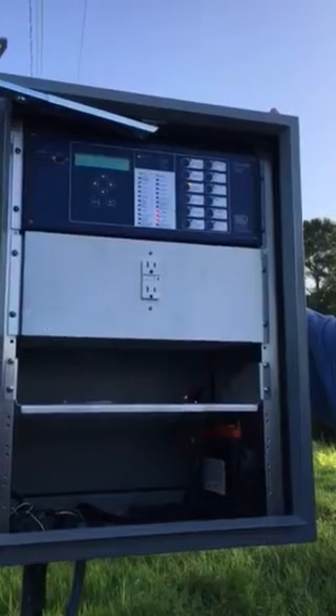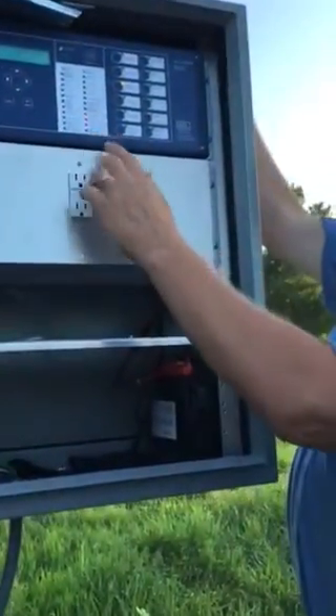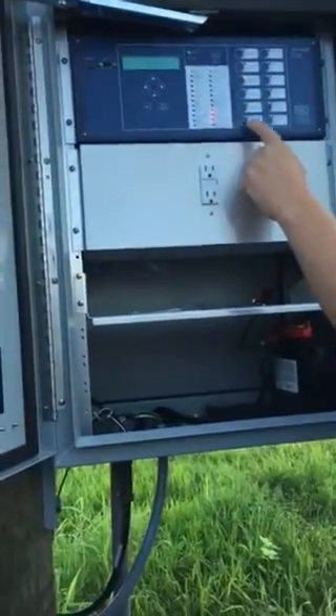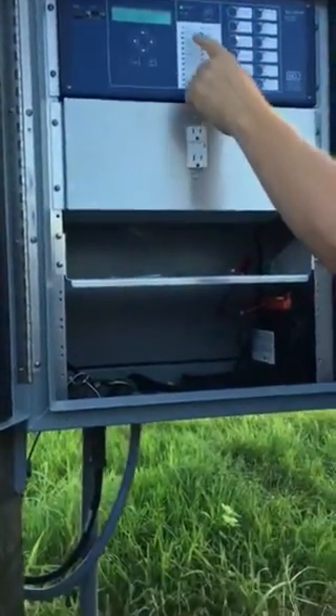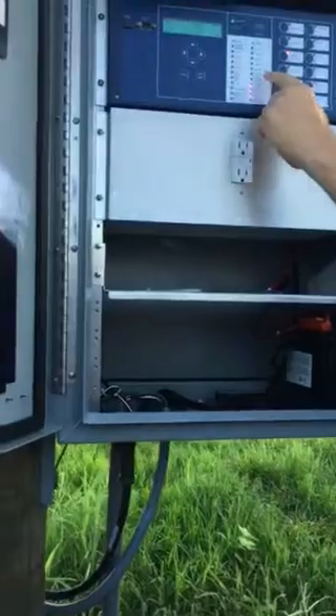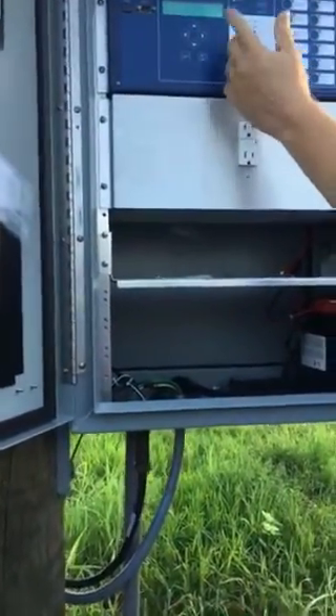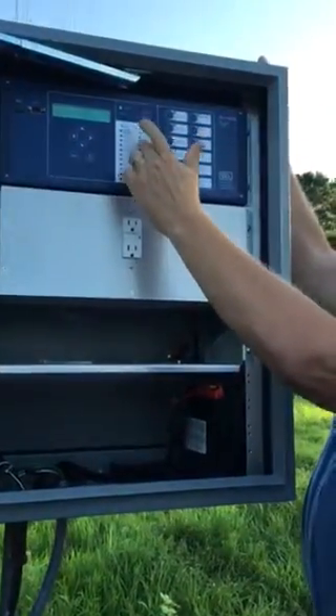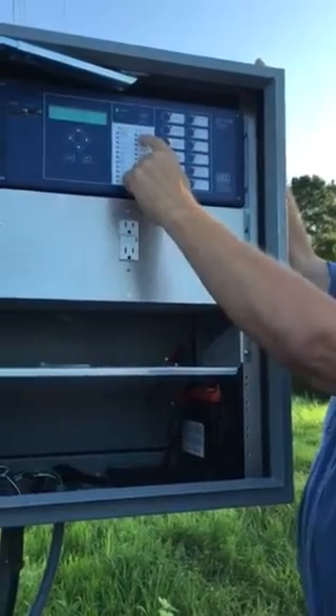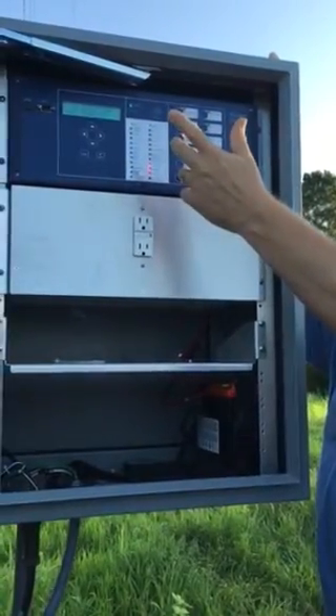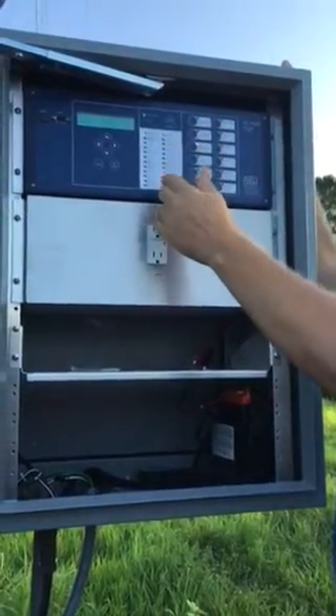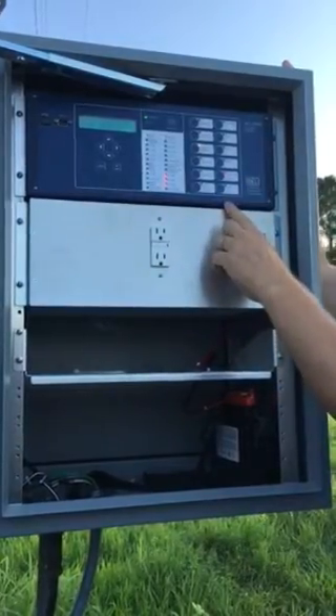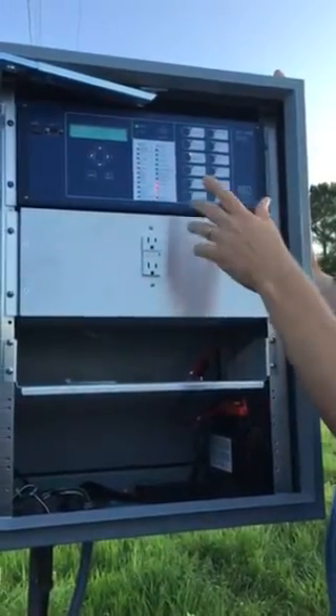So, like I said, that's another call for engineering to see what they want to do on that. But automatically, if you push a button to trip or it sees a fault, all three of these are going to lock out. If it doesn't have a fault and you just push a button, it's just going to lock out. Your reset light right here will click. And then when you go back in and push it back in to close, you're going to hear the breaker close if you're out here.